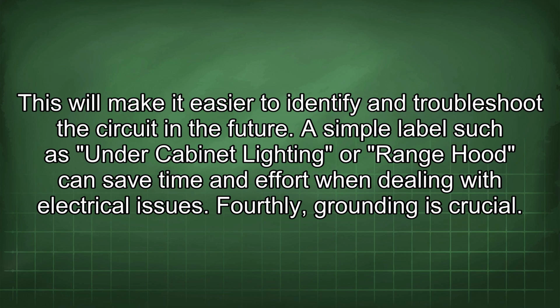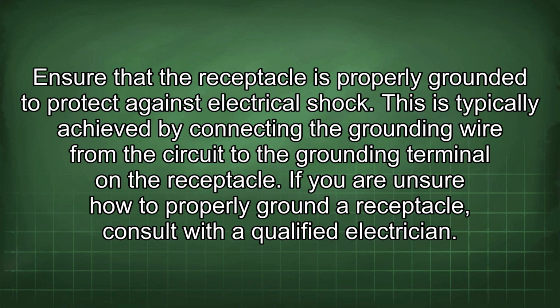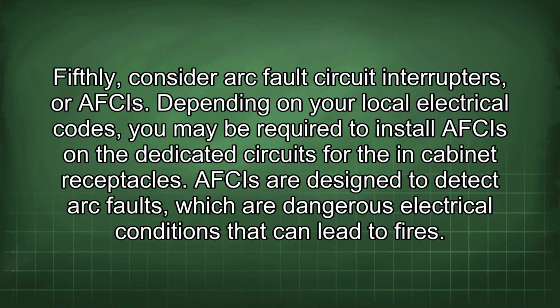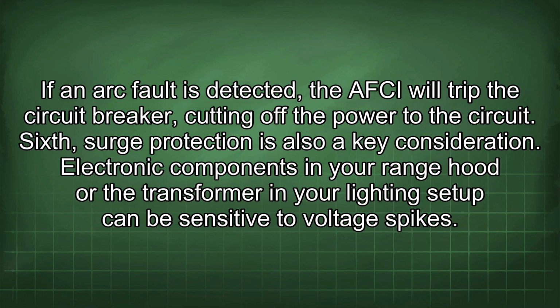Fourthly, grounding is crucial. Ensure that the receptacle is properly grounded to protect against electrical shock. This is typically achieved by connecting the grounding wire from the circuit to the grounding terminal on the receptacle. If you are unsure how to properly ground a receptacle, consult with a qualified electrician. Fifthly, consider arc fault circuit interrupters, or AFCIs. Depending on your local electrical codes, you may be required to install an AFCI on the dedicated circuits for the in-cabinet receptacles. AFCIs are designed to detect arc faults, which are dangerous electrical conditions that can lead to fires. If an arc fault is detected, the AFCI will trip the circuit breaker, cutting off the power to the circuit.